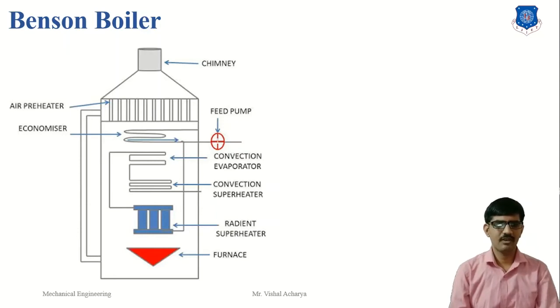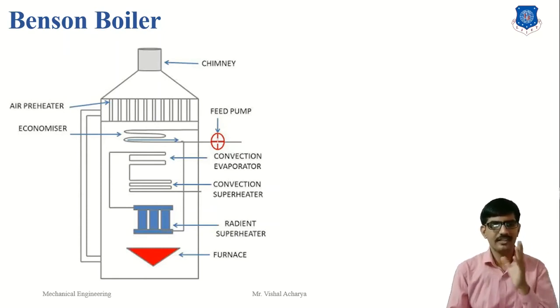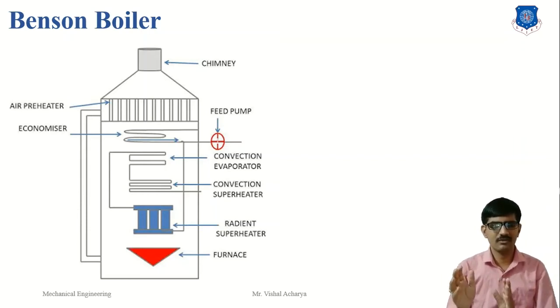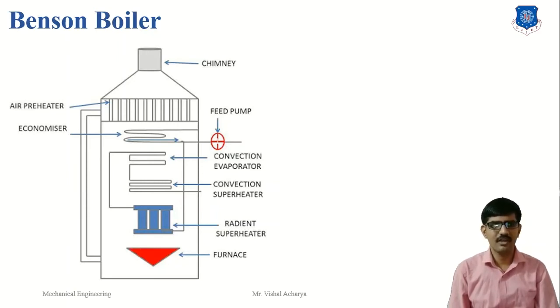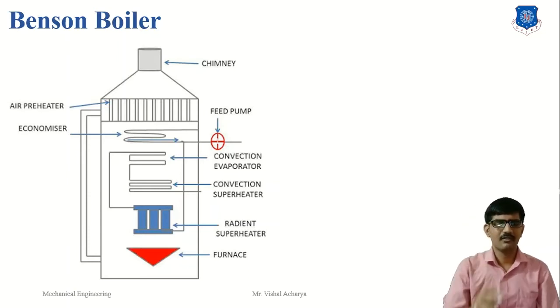The advantages of the Benson boiler: it is a drumless boiler, hence the weight is 20% less compared to other boilers; it is light in weight and occupies a small floor area; explosion hazard is almost negligible due to the use of smaller diameter tubes; it can be started very easily within 15 minutes; it avoids bubble formation due to supercritical pressure; transportation is very easy; and it can achieve thermal efficiency up to 90%. The average operating temperature is 650°C, pressure is 250 bar, and generating capacity is 135 tons per hour.